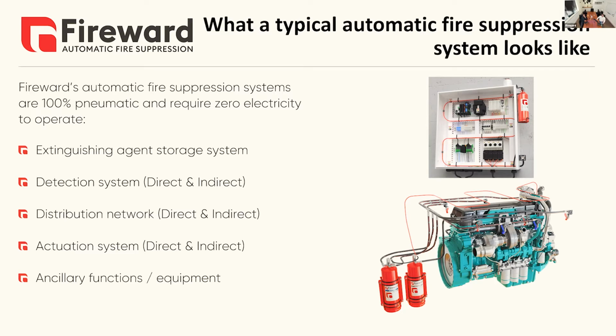And the point I want to emphasize, which we talked about, is that there is no electricity required to actuate the system. It operates on a differential pressure. What that means in English is that once the tube ruptures and loses the air within the red tube you see on the screen, it activates the valves to then release the agent. So it's a completely intrinsically safe system that doesn't require any electric and cannot fail to go off when there is a fire detected. Its default function is to activate when there's that pressure loss. So we're not relying on puncturing a cartridge and supplying pressure to the system. It's already ready to go and gives you that peace of mind.